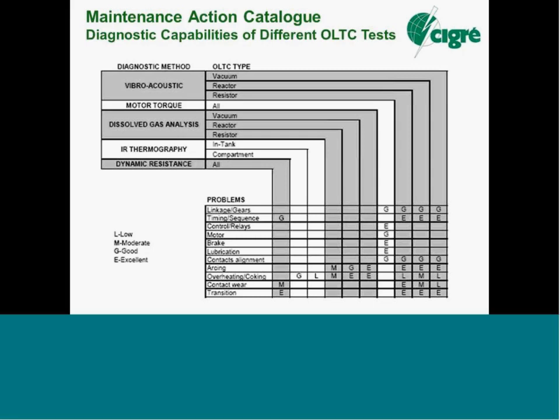Tap changer tests. We have this diagram for two types of tap changer: the resistor type and the reactor type. You need to familiarize yourselves with different types of tap changers, but the most common one is the high-speed resistor type that we typically use here in Australia. And the diagnostic methods: vibroacoustic, motor torque, DGA, IR thermography, dynamic resistance. For different problems, listed down that left-hand column, it shows which diagnostic method is good, excellent, or maybe of low or moderate use in detecting the particular problem in a particular type of tap changer.